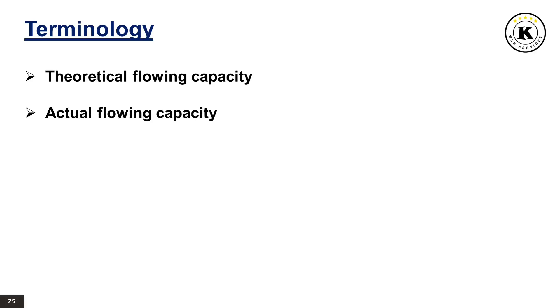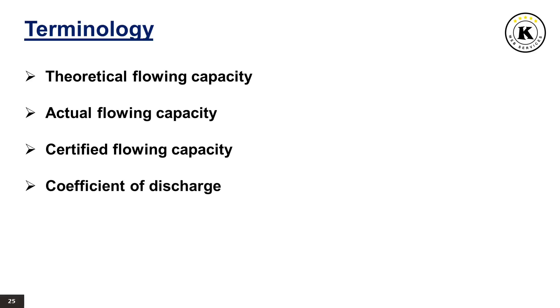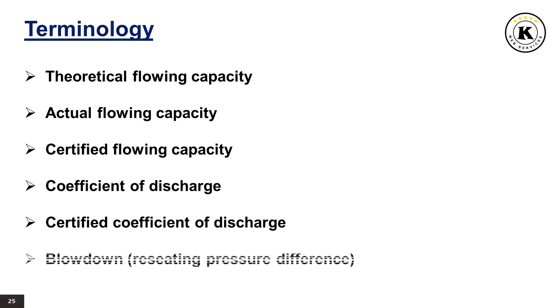Actual flowing capacity is the flowing capacity determined by measurement. Certified flowing capacity is actual flowing capacity reduced by 10 percent. Coefficient of discharge is the ratio of actual to the theoretical discharge capacity. Certified coefficient of discharge is the coefficient of discharge reduced by 10 percent, also known as derated coefficient of discharge. Blowdown or reseating pressure difference is the difference between actual popping pressure and actual reseating pressure, usually expressed as a percentage of set pressure or in pressure units.